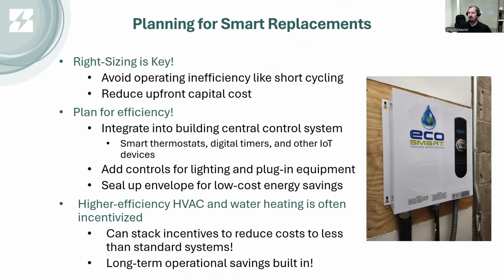Plan for efficiency—try to integrate any new equipment into existing building automation systems if you can, or ensure they have automation capability as part of installation, such as smart thermostats and digital timers for lighting. For Internet of Things devices like smart thermostats on electrical panels, you can use load shedding technologies to avoid panel upgrades by turning off unnecessary equipment to run more prioritized circuits. Also add controls for lighting and plug-in equipment, such as occupancy sensors, daylight sensors, and time clocks.